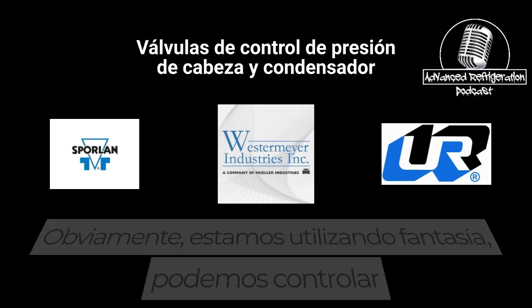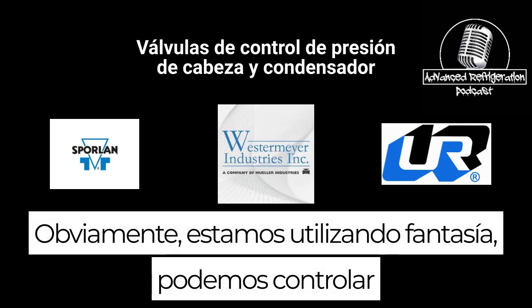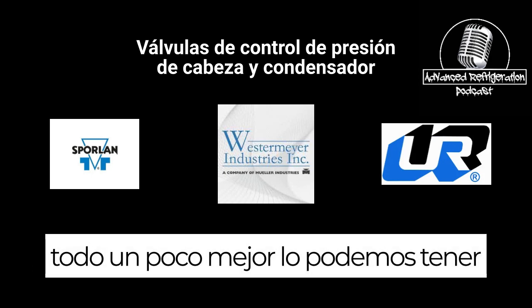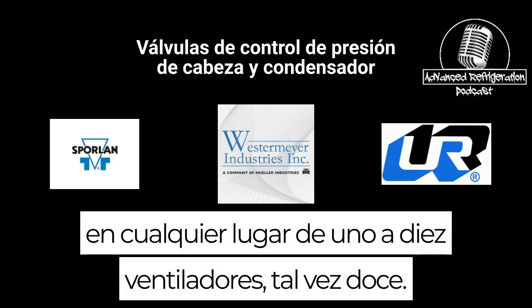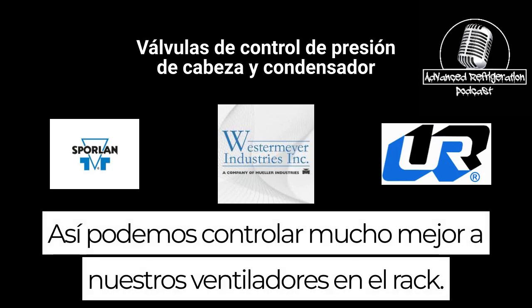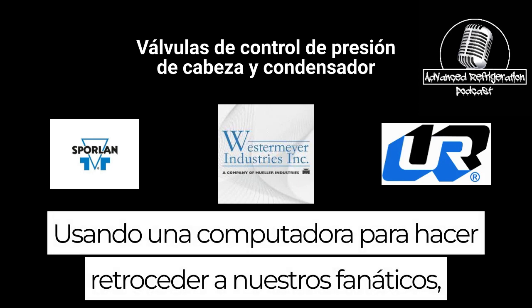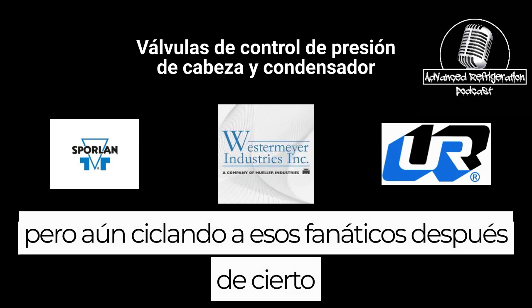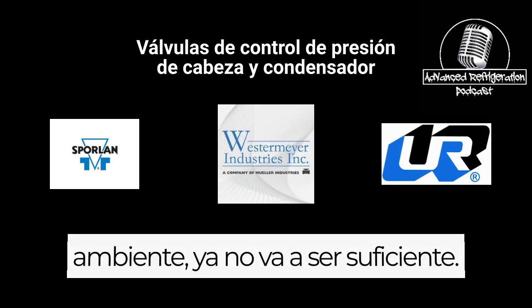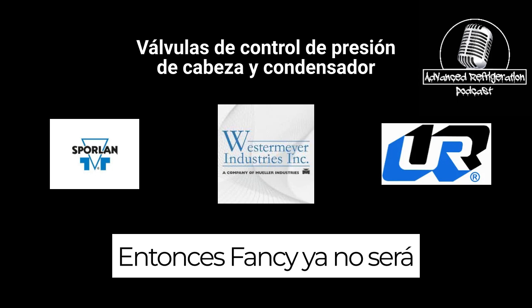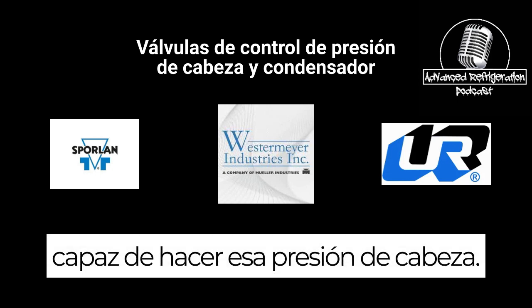On a rack, I mean, obviously we're utilizing fan cycling. We're able to control everything a little bit better. I mean, we may have anywhere from 1 to 10 fans, maybe 12. So we can control our fans a lot better on a rack using a computer to step our fans back. But still, cycling those fans after a certain ambient, it's no longer going to cut it. So fan cycling will no longer be able to make that head pressure.